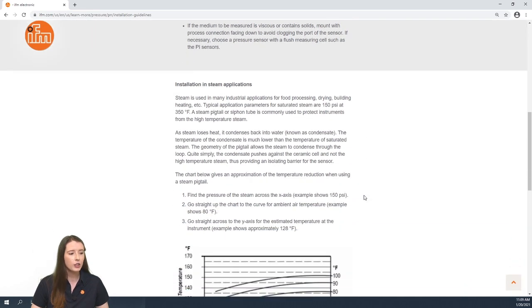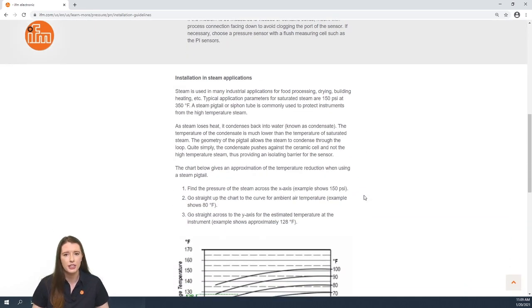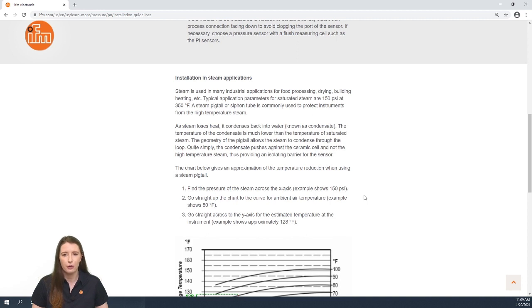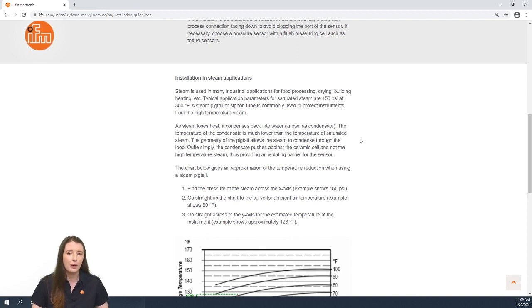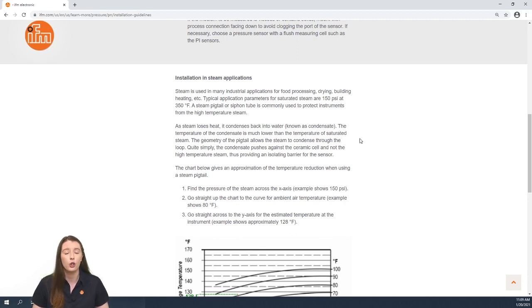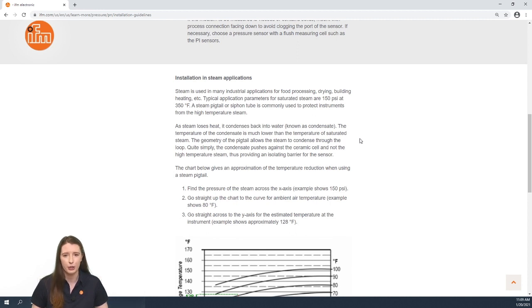Next we talk about using these sensors in steam applications. Since steam is a high temperature, we recommend using a steam pigtail or siphon tube to protect the sensor from these high temperatures. In this paragraph, we talk about the technology that is used with our steam pigtail because it converts steam back to water known as condensate and this lowers the temperature of the media to protect the sensor.